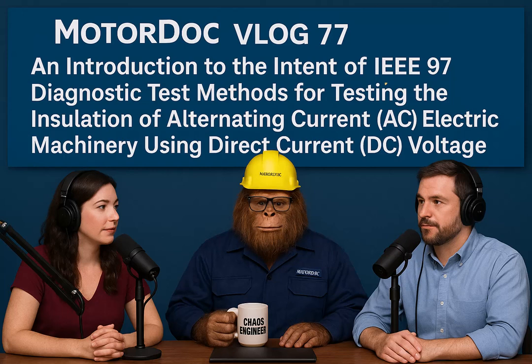Okay, so the DCR test isn't just about hitting a maximum voltage. Yeah. The shape, the slope, the linearity, where it becomes nonlinear. It all tells a detailed story about the insulation type, moisture, aging, delamination, contamination. It really does provide a rich signature. Okay, now let's move on to the second key test, the Polarization Depolarization Current test, PDC.